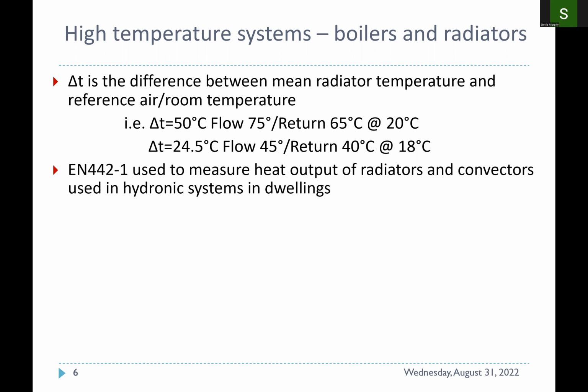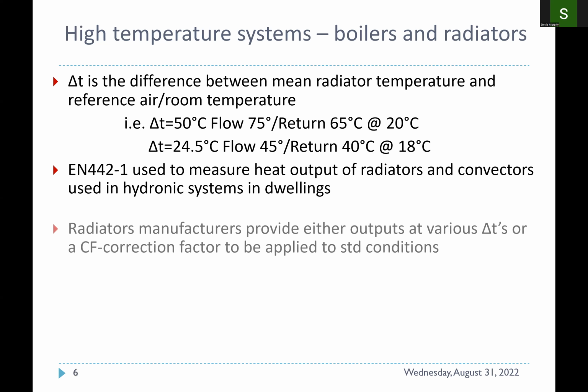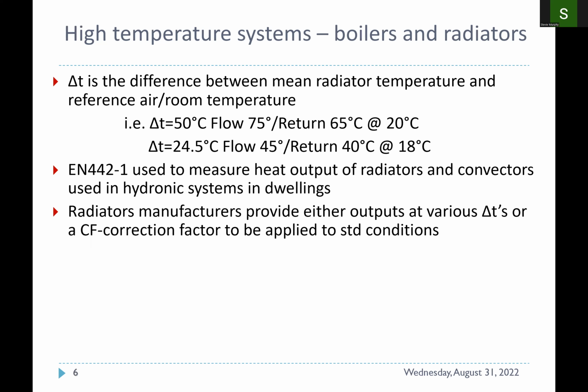So we use EN 442-1, which is a standard to measure radiator and convector outputs in wet systems. That's what most manufacturers will use to determine these outputs. To calculate the output of a radiator at various delta Ts, we use what is called the correction factor. Most of the time we will get from every manufacturer an output at a delta T50, and we consider that the standard, the benchmark, and to that we then apply the correction factor depending on the various flow and return temperatures and room temperature that we've used.